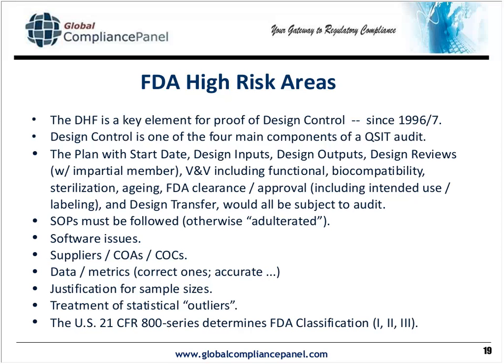Treatment of outliers. In the past, there was a tendency to blow them off. If you had one data point way out there and the rest in a normal distribution, there's a tendency to dismiss it as an aberration. Well, the FDA has recognized that that is telling you something, and you have to at least analyze it and discuss it. And you may be able to, in a sense, buy it off, so to speak, in your discussion, and that may be acceptable. However, bear in mind that you want to monitor for that, because it's possible that outlier is telling you something that may infrequently occur and may result in some CAPA issues and maybe even a recall. So you certainly want to monitor it and make sure that your understanding of what caused that is in fact the correct understanding in a root cause.